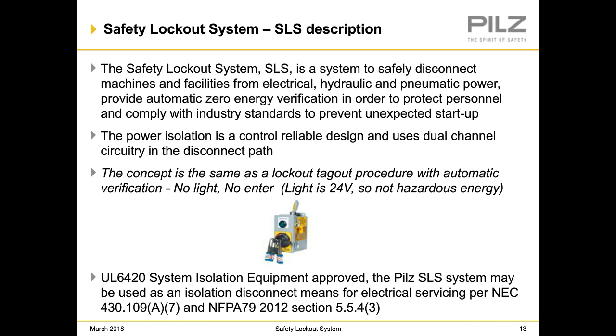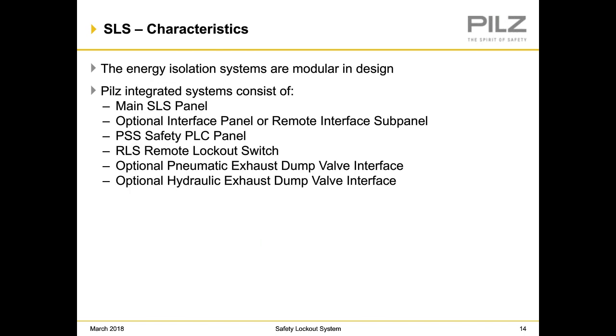UL6420, system isolation equipment approved, the Pilz system may be used as an isolation disconnect means for electrical servicing per NEC 430.109 and NFPA 79-2012. And we'll show some other references to standards later in the presentation. The energy isolation systems are modular in design. You have a main panel, you have an optional panel or remote interface subpanel, you have a safety PLC, then you have the remote lockout switches, you have optional pneumatic exhaust dump valves, and also optional hydraulic exhaust dump valve interfaces.